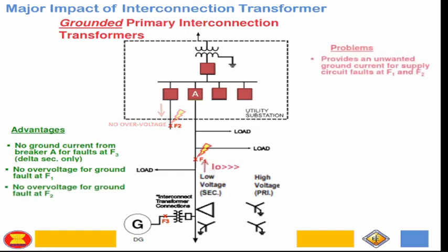Okay? And also, the disadvantage is that it provides an unwanted ground current for a fault at F2 and F1. Meaning, if there is a fault here in your adjacent feeder, your coordination is now a sum of the fault contribution from the grid and the contribution from the DG. Before, in a radial system, when it was still centralized and we did not yet entertain distributed generation in the line, the coordination was from the high side, the main substation breaker, then coordinated with the feeders. Now you must consider the fault contribution from the DG and also from the grid. So the system is now more complex.